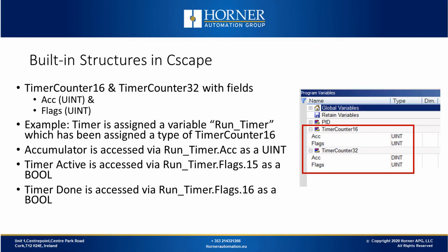Now we'll discuss some built-in structures in Cscape. There's a pre-configured structure for 16-bit timers and counters, and 32-bit timers and counters. There's a field for accumulators and a field for flags for both of them. For example, a timer is assigned a variable run_timer, which has been assigned a type of timer counter 16. If you want to access the accumulator, you can access that from run_timer.acc, which is an unsigned integer for a 16-bit timer and a double integer for a 32-bit timer.